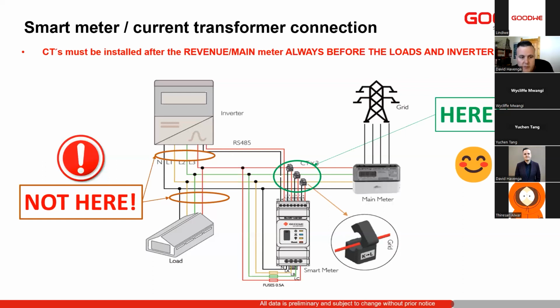You'll see also where we install the CTs, and the supply to the meter is very important. So as close to the utility meter as possible, our voltage supply, and then the CTs as close to the utility meter as possible. Never between the inverter and loads, never below the inverter. We should also never power the meter from the backup.